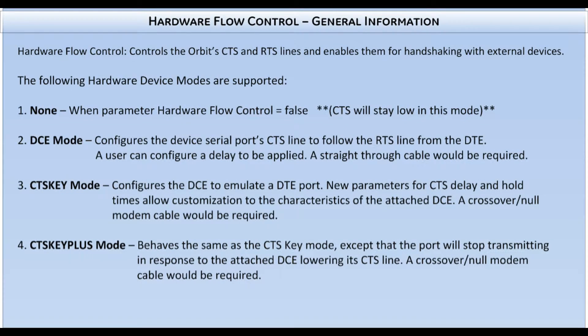When hardware flow control is disabled, there is no serial flow control done on the port. When enabled, the Orbit MCR supports three modes to control the serial port lines: DCE, CTS key, and CTS key plus. Each of these modes configures the Orbit's RTS and CTS lines to operate in a slightly different way.